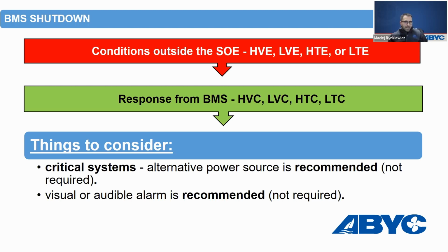It's not the requirement, but it's something worth considering. Also, there is a recommendation for a visual or audible alarm before the BMS disconnects the battery. It's not a requirement, it's a recommendation. Not all shutdowns are easy to predict. In case of overcharging and over-discharging, it's a little bit easier because you can see that the voltage is rising, and it will reach the limit soon. But for example, in case of an external heat source, it might be difficult to predict. That's why we cannot require that alarm.